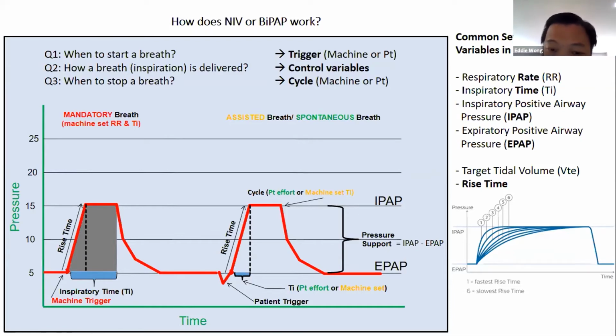Okay, normally rise time is a common setting where the ventilator provider, when they come to your house, if you complain of any discomfort, after they check that you do not have any secretion problem, you do not have any connection problem on the tubing and mask, and you still complain about discomfort, the only setting they are normally allowed to set is the rise time. They are not allowed to change the EPAP, IPAP settings, because this is a doctor's prescription. But the rise time, normally they will help you set, or they will guide your family how to set the rise time, when you complain the air is entering your lung too fast, or too slow.